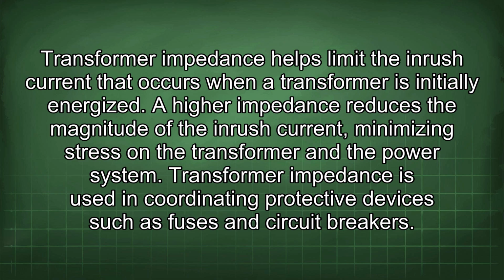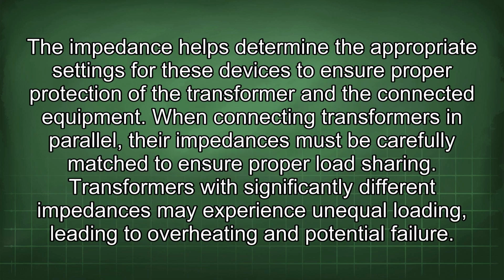Transformer impedance helps limit the inrush current that occurs when a transformer is initially energized. A higher impedance reduces the magnitude of the inrush current, minimizing stress on the transformer and the power system. Transformer impedance is used in coordinating protective devices such as fuses and circuit breakers. The impedance helps determine the appropriate settings for these devices to ensure proper protection of the transformer and the connected equipment. When connecting transformers in parallel, their impedances must be carefully matched to ensure proper load sharing. Transformers with significantly different impedances may experience unequal loading, leading to overheating and potential failure.